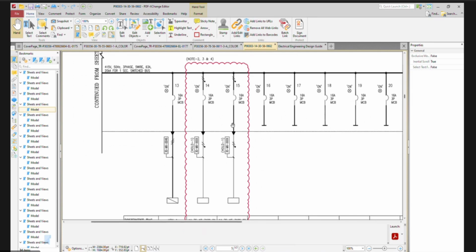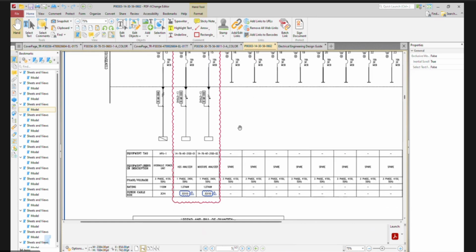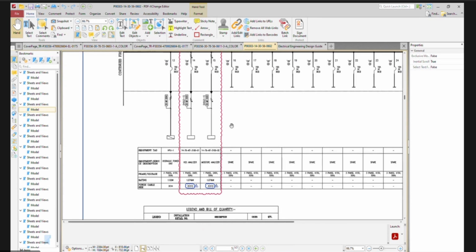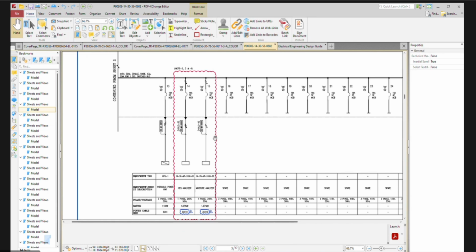If you allow me, let me put my point here. This is just an analyzer, not relevant like a lighting or socket load. Generally in ADNOC onshore, for our analyzers we will never give an ELCB circuit as a feeder. It will be fed from a normal MCB only, as I explained earlier. ELCBs are generally provided for small power requirements like lighting and plug-in/plug-out socket outlets. That is the general practice. If it's recommended as a strict requirement for ELCB, then we need to think about it, but for analyzers in general we will never give ELCBs.